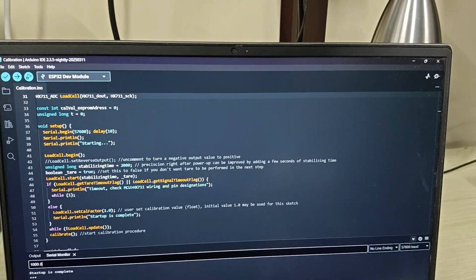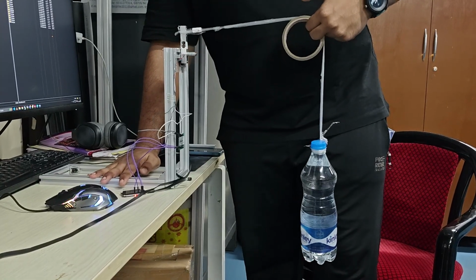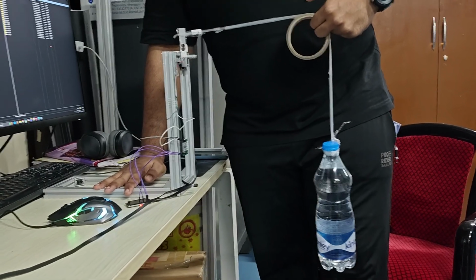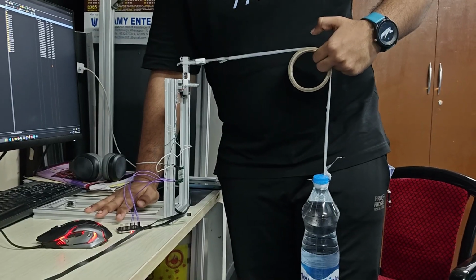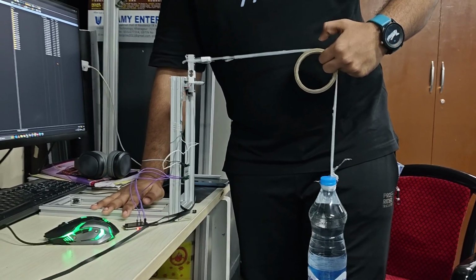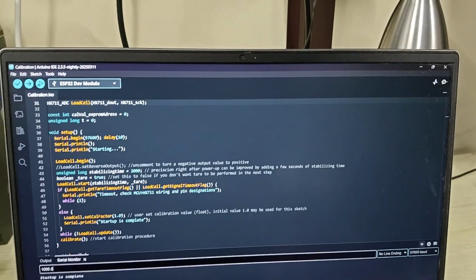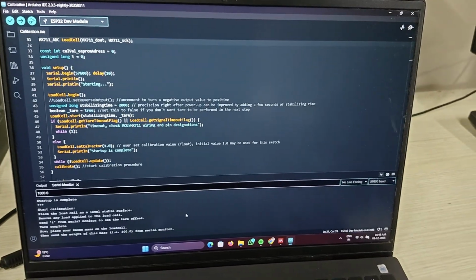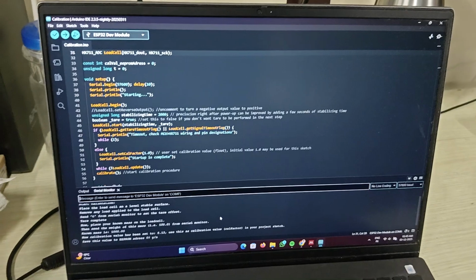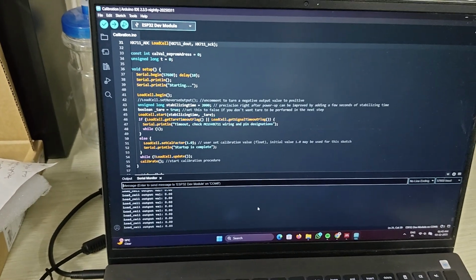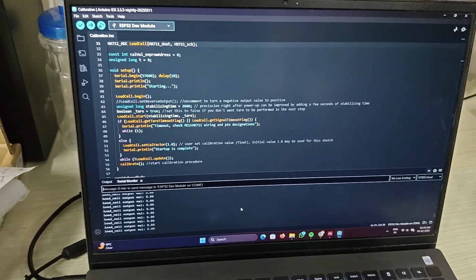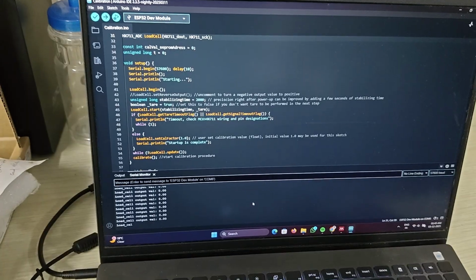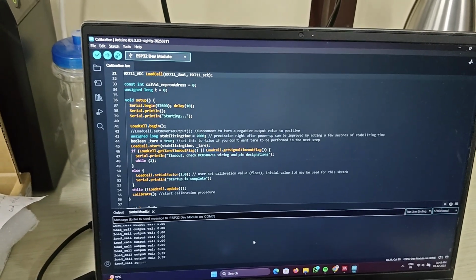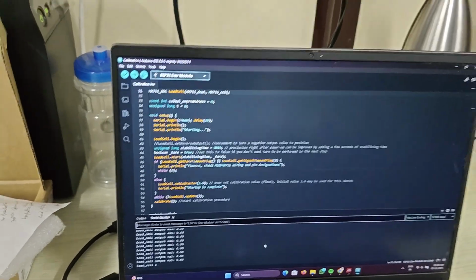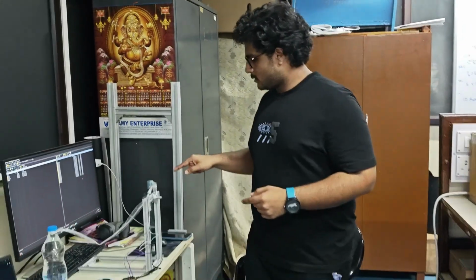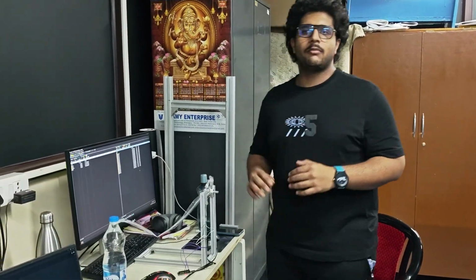And when this bottle is let free, the load cell is deflected in a cantilever fashion, and the reading has been given as 1000 grams because this load cell gives the readings in terms of grams, because load cells are usually made for measuring mass and not weight. So any thrust we measure will be in terms of mass from this particular system, and this is how the calibration process is done.